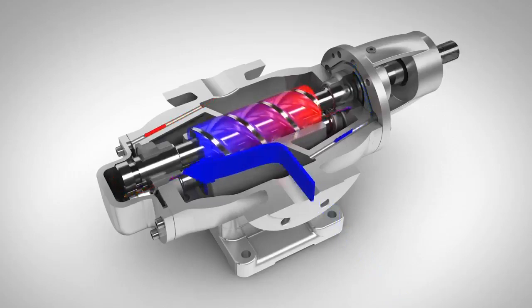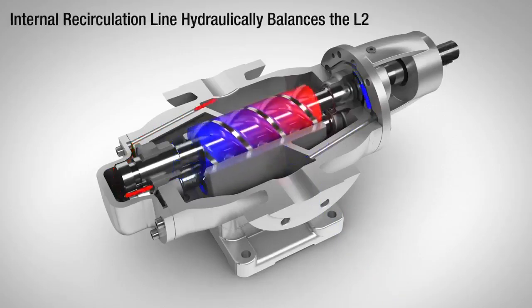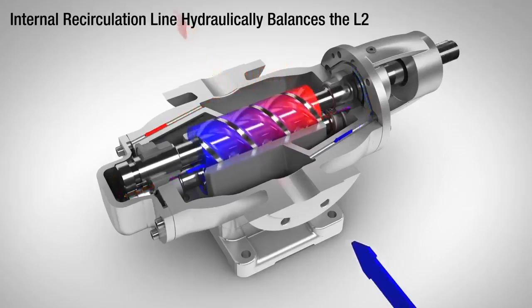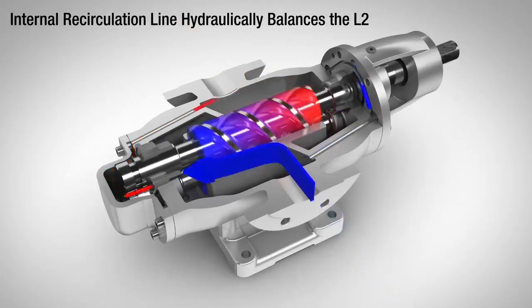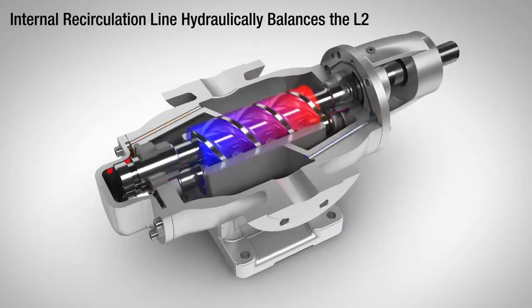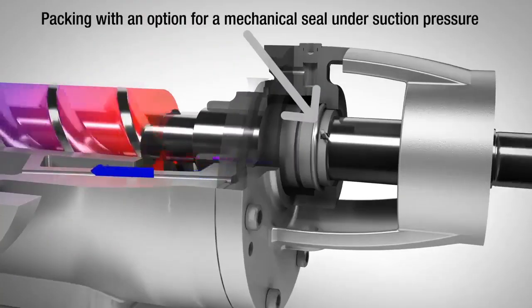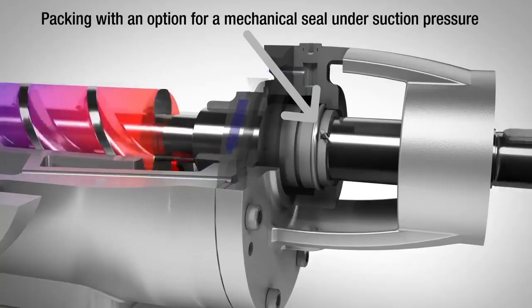The pump is hydraulically balanced with an internal recirculation line. Due to this recirculation line, bearing loading is reduced, eliminating the need for thrust plates and extending the life of the bearing. The packing area, or mechanical seal, is only subject to suction pressure because of the balance line.